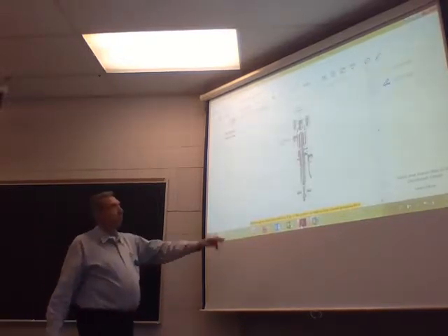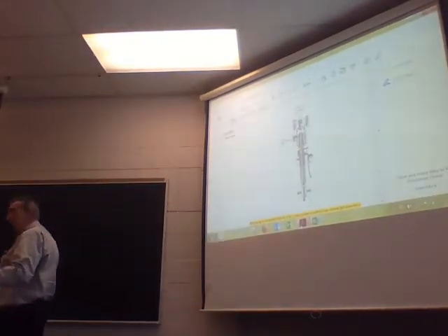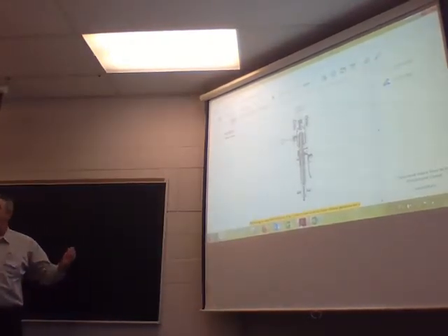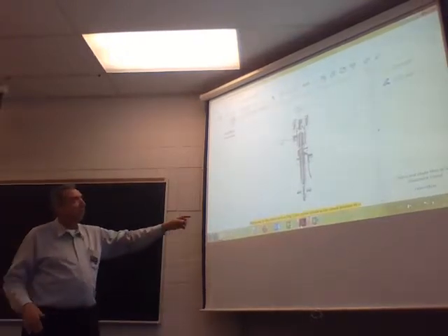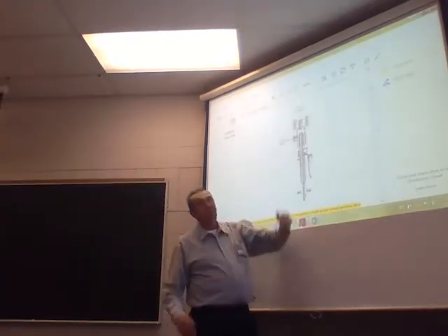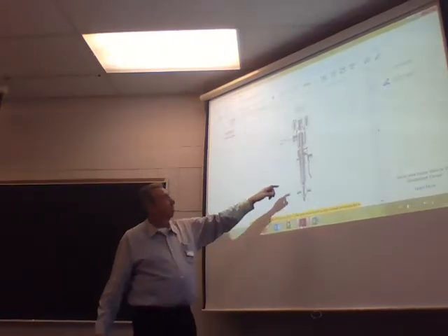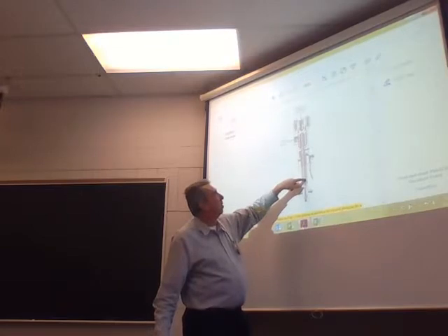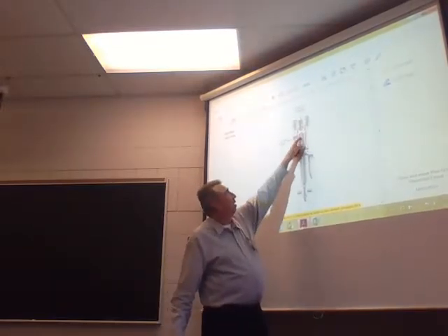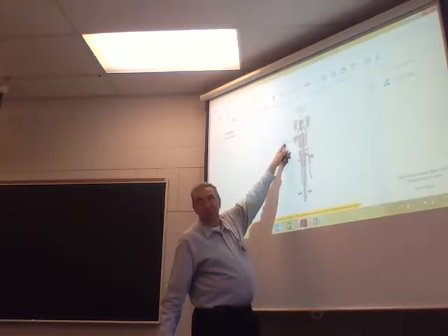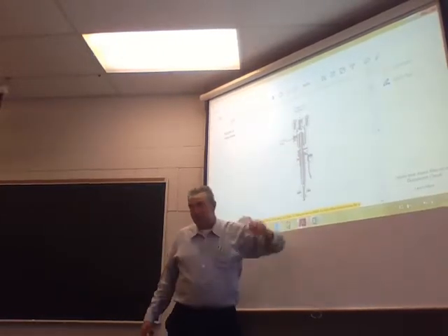So I'm going to talk you through this because you can read all this, but I'll talk you through it. I've got this hooked up to my air receiver. All right. 100 psi is what I want because I just like 100 as a number because it's easy to work with, right? So I want 100 psi. My receiver starts to go above 100 psi. You can see where the pressure will now overcome the tension of the spring and will allow air to go out through this inlet valve. Got that so far?